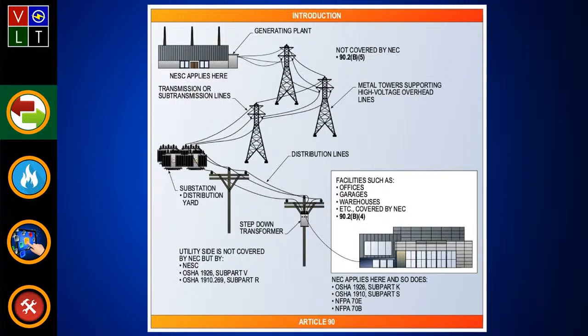And they're not separated by voltage - that's another big myth, that there's a low voltage standard and a high voltage standard. That's not correct. All the standards apply to anything 50 volts or greater. It's the equipment that separates them.